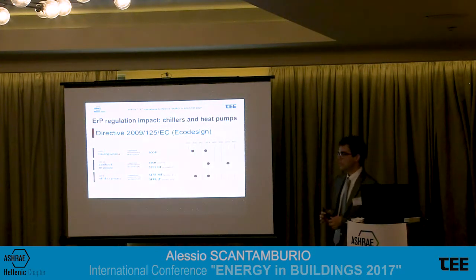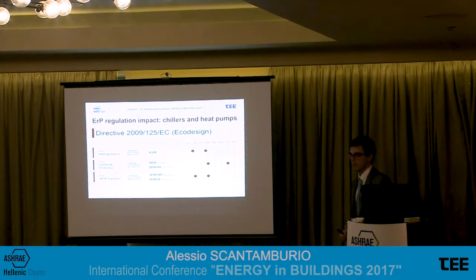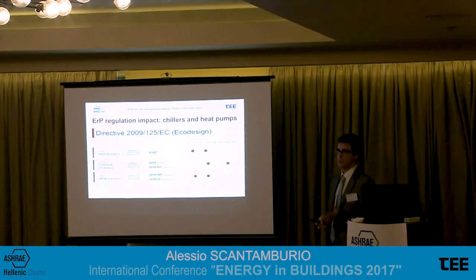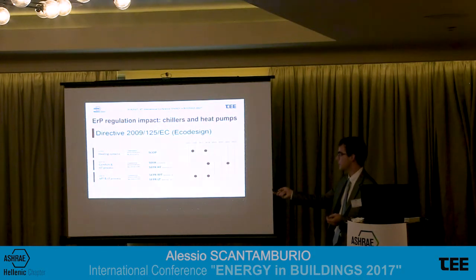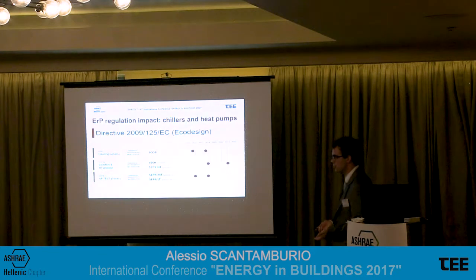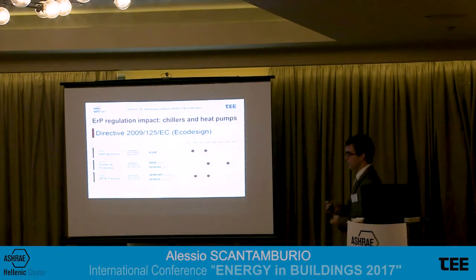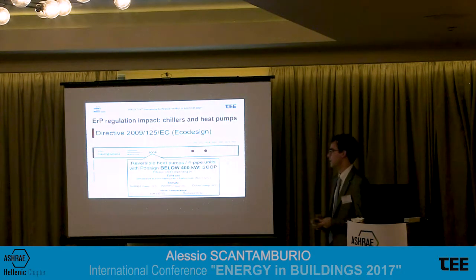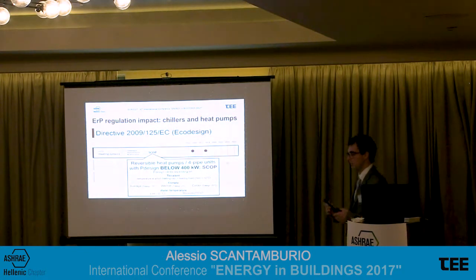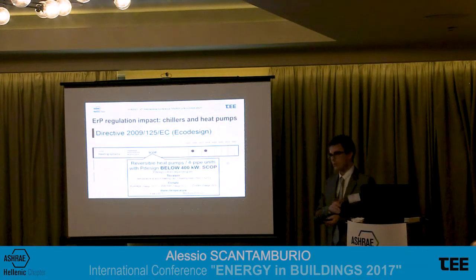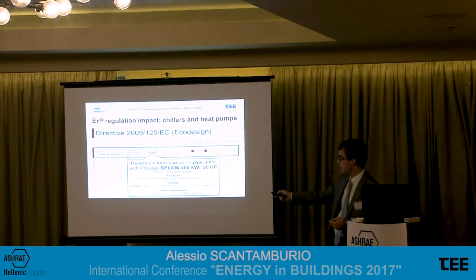We know that 4-pipe units, or in general reversible heat pumps, are able to produce hot water but also cold water, reversing the cycle. So what must they be compliant with? With the SCOP, because they are heat pumps, or with the SEER, because they are able to produce cold water? The regulation is not so clear on this point, but the key is this one. If the reversible heat pump, or the 4-pipe unit, or every piece of equipment that is able to produce cold water but also hot water, not at the same time or also at the same time, has a design capacity below 400 kilowatts, then it must be compliant with the SCOP.